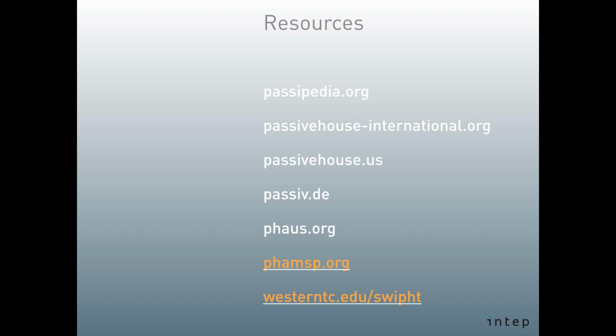Follow up in the summer, you could have that then dehumidified. No, the question was, can you have it be dehumidified? No, the ventilator doesn't do any of that. This is an HRV setup. It has no moisture transfer potential whatsoever. So it doesn't do any of that. The dehumidification comes out of the heat pump system. Yeah. They're not ducted together.